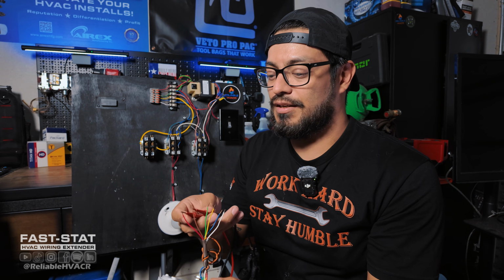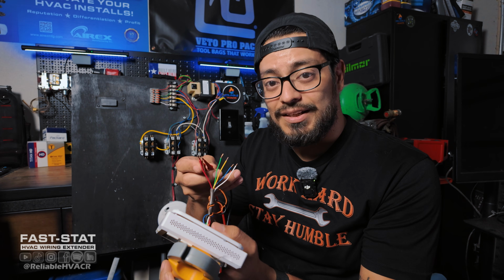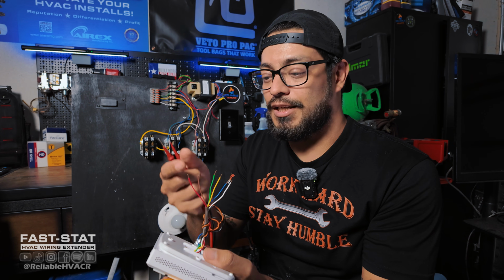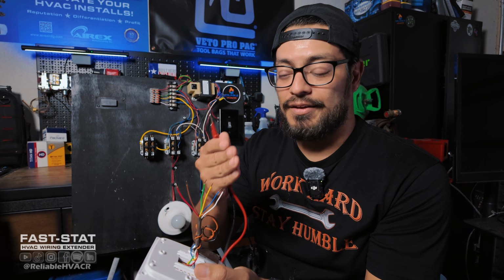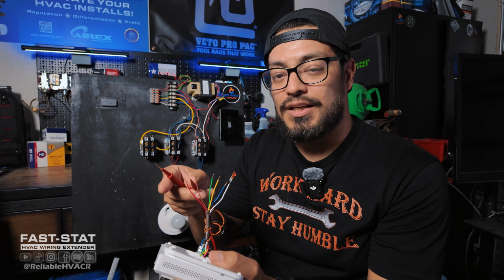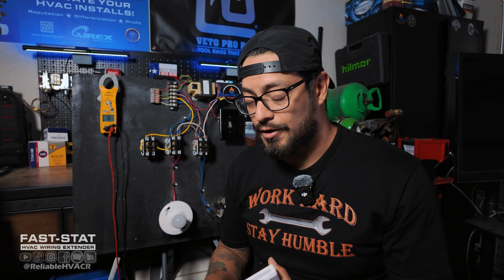So then you're checking, do I have continuity to each wire? Because I shouldn't. Each wire is its own path. And then from there, check each end to ground. So typically when I'm checking, and I feel like I have an issue with the wiring, or I want to eliminate that thought, I will remove the faceplate.